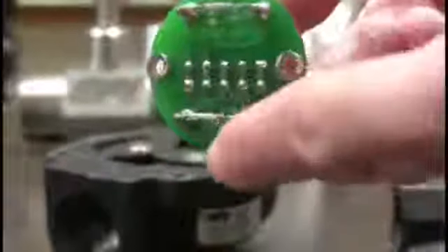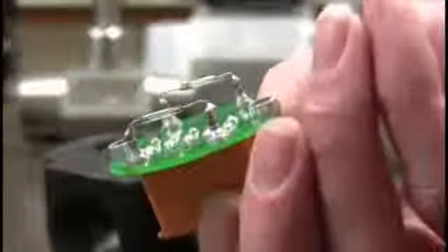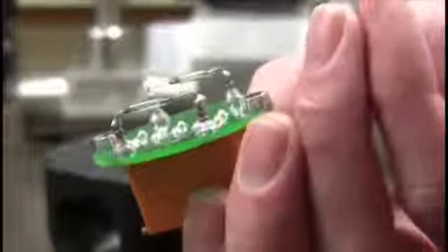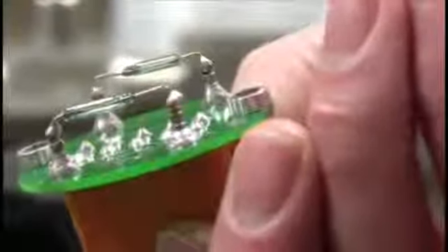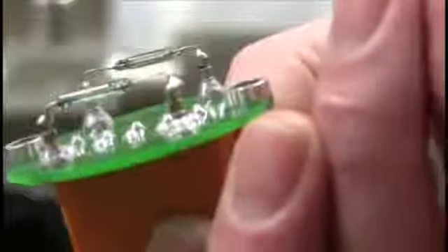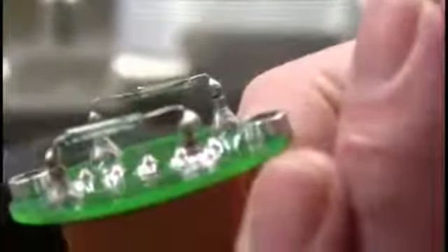Two reeds. One here is like a little glass tube, and inside that glass tube is a real thin wire, and that thin wire will bend down every time the rotor goes underneath it, and the magnet draws it down, and it'll touch a stiff hard wire, and that gives it continuity. And then once the magnet's gone, the reed, or the thin wire, straightens back out.